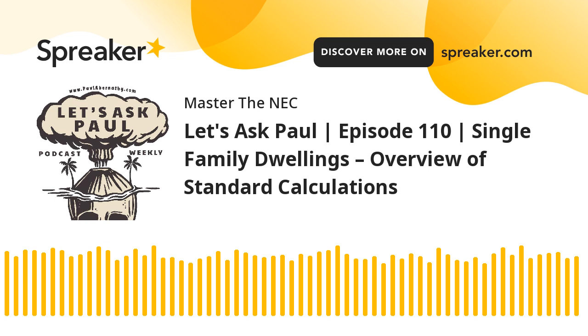Now, since we're doing a standard method, 220.54 says that you're going to use 5,000 watts, which is synonymous with VA in this example. So anytime you can start converting it over to VA, go on and start doing it. So 5,000 watts or the nameplate, whichever is larger, in the standard method, that's how you do it. Now, in the optional method, you just take the nameplate. But we're not doing the optional. We're doing the standard.